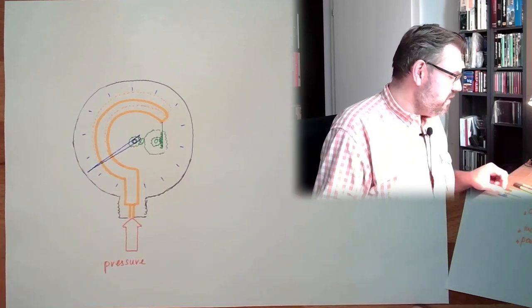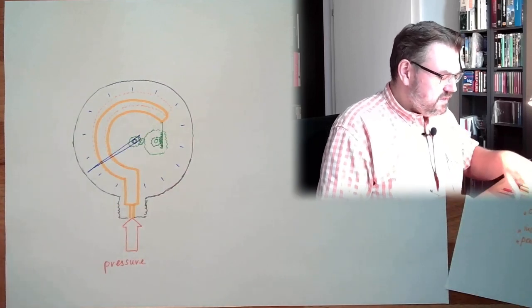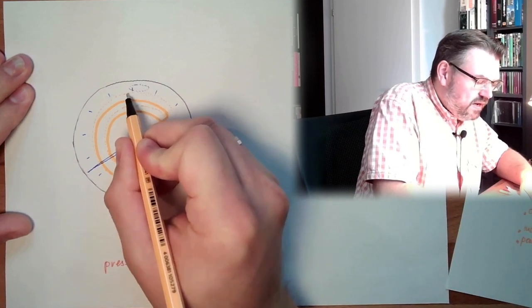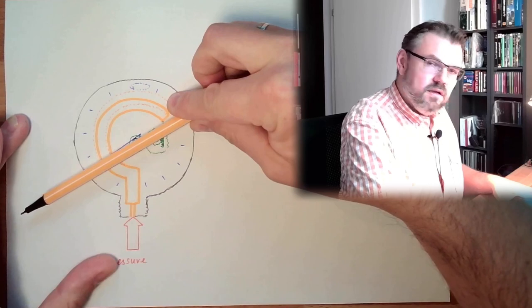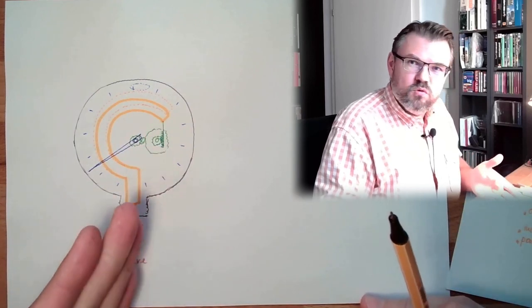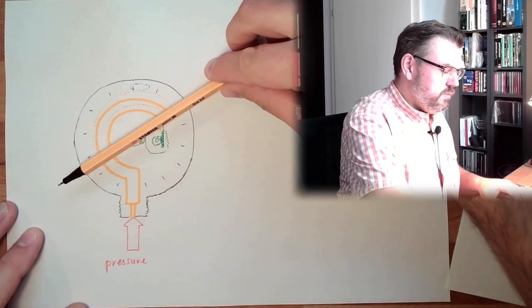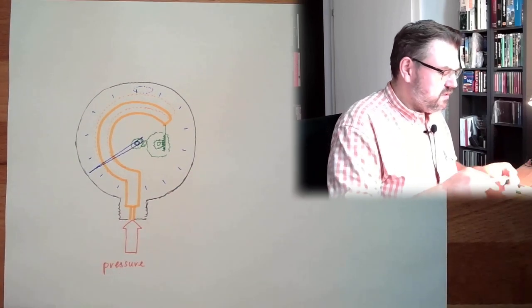Maybe you have already seen a manometer where it's a little bit shaky inside. What is usually done there is that the internals are liquid filled. You usually see somewhere a small air bladder inside, and the rest is filled with some liquid, which adds friction and causes it to stand still. So if there's noise and the pressure is pulsating, we would see this on the pointer. If it's liquid filled, it will be still. So this is filtering — filter the signal. A mechanical filter, adding friction. Of course the dynamic behavior is then not that good.